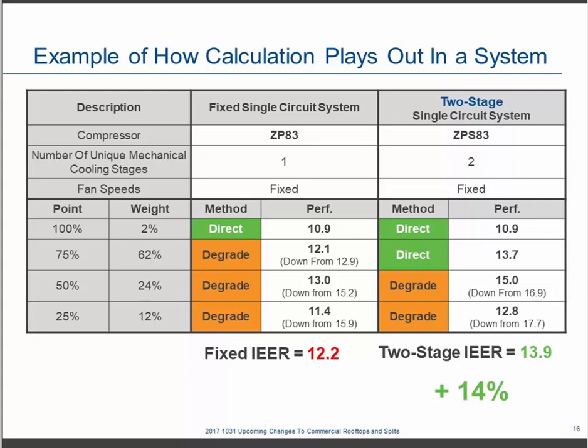You could also put in two smaller fixed-capacity compressors. There's a lot of flexibility with multiple compressors in how you hit different weighting points. If you mix and match compressor sizes, you could hit the 50 percent point directly and eliminate that degradation. But trade-offs include size constraints — can you actually fit two compressors in a system? — plus extra tubing cost and piping complexity. Every application is going to be different.